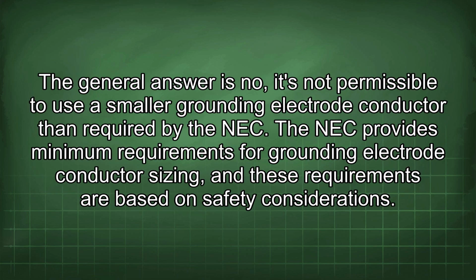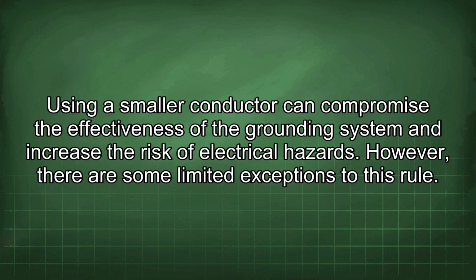It's not permissible to use a smaller grounding electrode conductor than required by the NEC. The NEC provides minimum requirements for grounding electrode conductor sizing, and these requirements are based on safety considerations. Using a smaller conductor can compromise the effectiveness of the grounding system and increase the risk of electrical hazards. However, there are some limited exceptions to this rule.